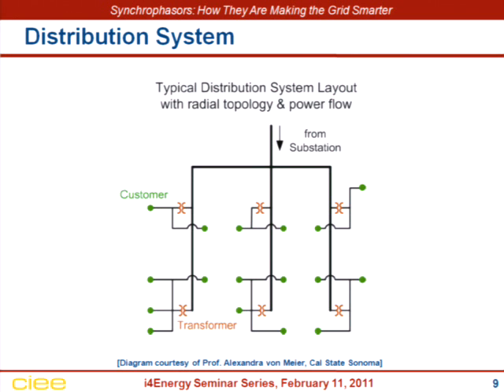Downtown San Francisco is a good example where they put in a networked feeder system to provide higher reliability and power transfer to the downtown office buildings. There you get into more of a transmission mentality in how you design and operate the system, with protection, reconfiguration, and multi-directional load flow depending on conditions. But that's fairly rare. Mostly, distribution serving customers is radial like this.